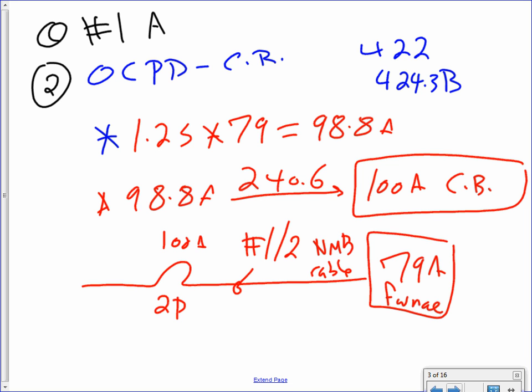I want to remind you, now we need to go put a disconnect right here. We need to put a disconnect right here, right? And we also need to pull the equipment grounding conductor. Don't forget that there's an equipment grounding conductor. Next. Right? I'm just redrawing what I drew in the beginning. No, nothing new.